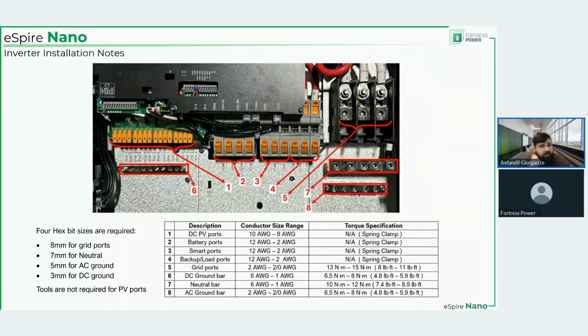For battery and backup and smart ports, you will need a screwdriver or some kind of a metal rod for that metal hole to open. I'm going to show you in a moment what the precautions there are as well. But more importantly, hex bit sizes required are given on the left for neutral, ground, and for grid. And you see here the conductor size range for each of these ports. This is very important. This will be part of the manual as well. And torque specifications for the cables that are actually going to be secured by the screws.